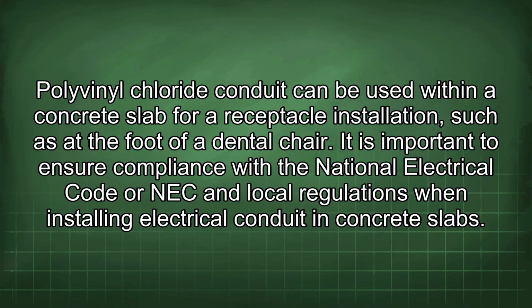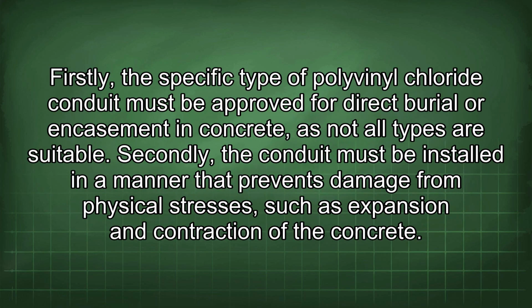Polyvinyl chloride conduit can be used within a concrete slab for a receptacle installation, such as at the foot of a dental chair. It is important to ensure compliance with the National Electrical Code or NEC and local regulations when installing electrical conduit in concrete slabs. Firstly, the specific type of polyvinyl chloride conduit must be approved for direct burial or encasement in concrete, as not all types are suitable. Secondly, the conduit must be installed in a manner that prevents damage from physical stresses such as expansion and contraction of the concrete.